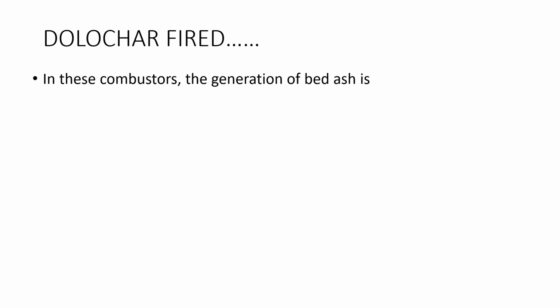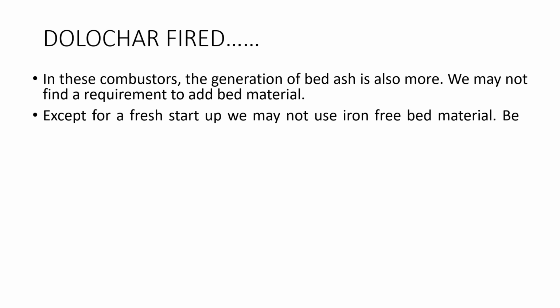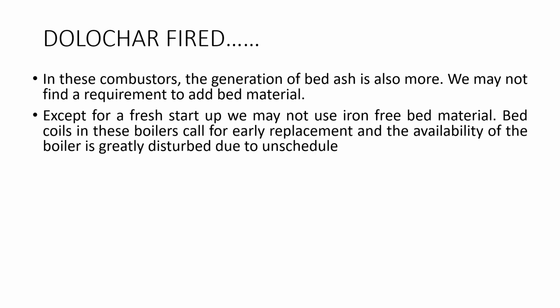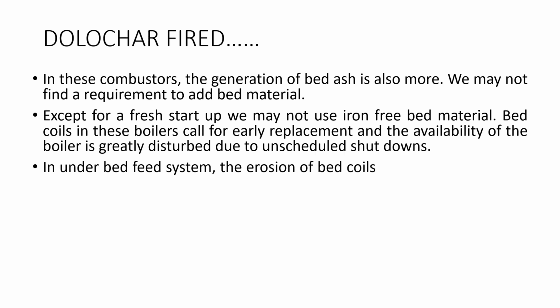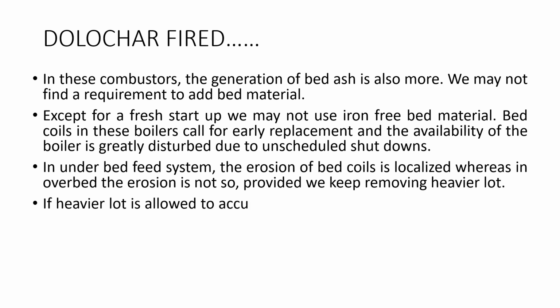Then in case of Dolochar fired boilers, in these combustors, the generation of bed ash is also more. We may not find a requirement to add bed material. Except for a fresh startup, we may not use iron-free bed material. Bed coils in these boilers call for early replacement and the availability of the boiler is greatly disturbed due to unscheduled shutdowns. In underbed firing system, the erosion of bed coils is localized, whereas in overbed, the erosion is not so, provided we keep removing the heavier lot.